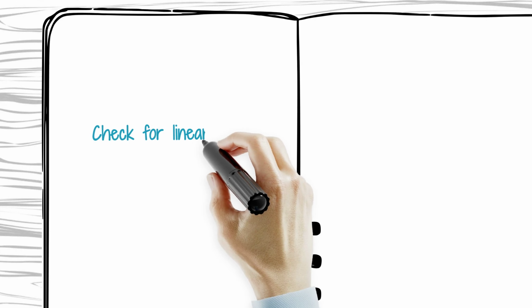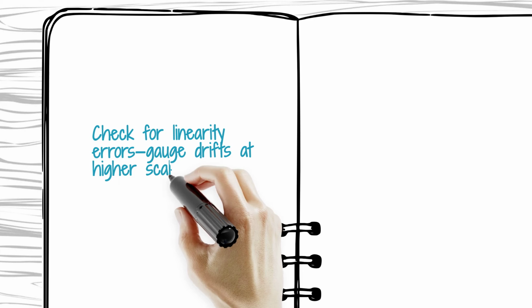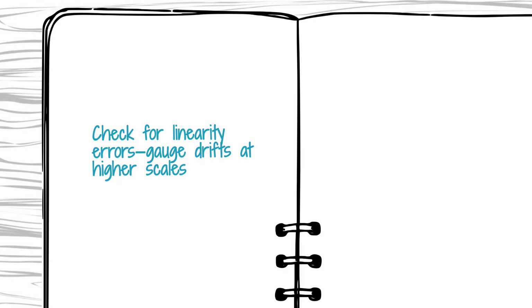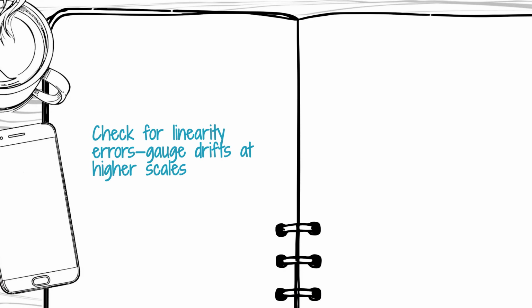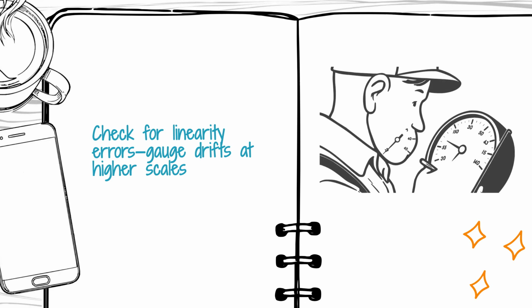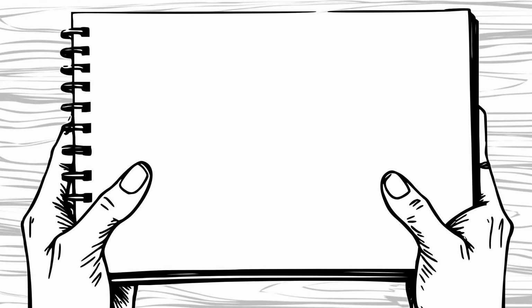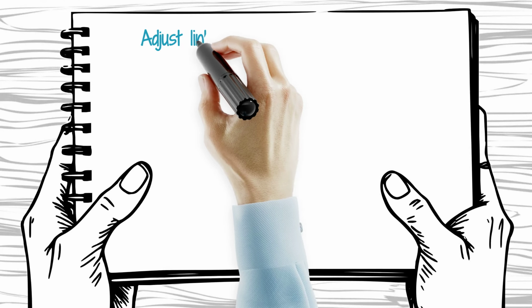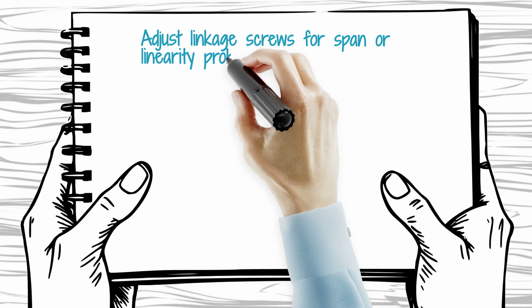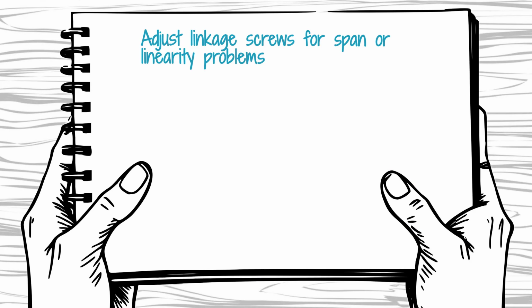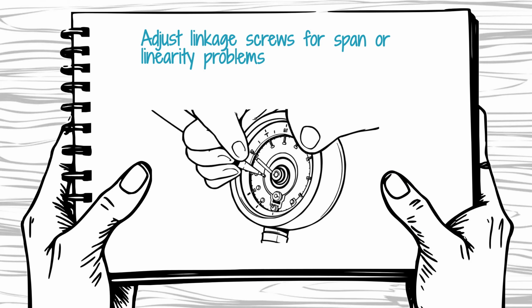end of the scale. If the error is consistent across the range, you may need to remove the bezel and glass to access the pointer. Use a pointer puller to gently remove the needle and reset it exactly on the zero pin. For more complex errors, such as span or linearity issues, you will need to adjust the internal linkage screws. Shortening or lengthening the linkage arm changes the sweep of the pointer relative to the Bourdon tube movement.